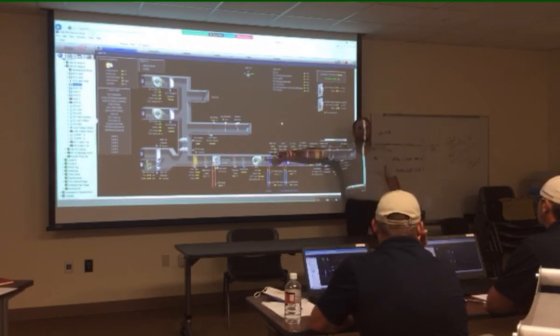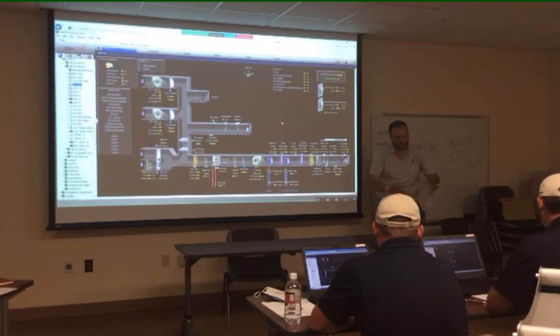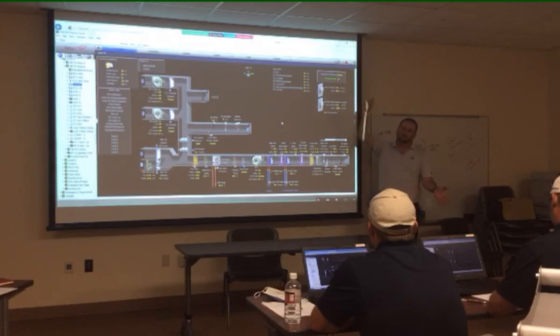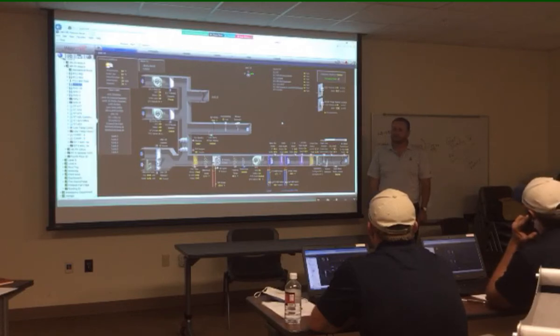But we're pulling outside air and putting air into the space because that exhaust fan's got to have air to relieve from somewhere. If we didn't do that, it's going to pull air from all the outside surrounding spaces. Makes sense? So in order to evacuate that smoke, we're going to pull in outside air and turn the exhaust fans on. Maintain this pressure. Any questions on that?